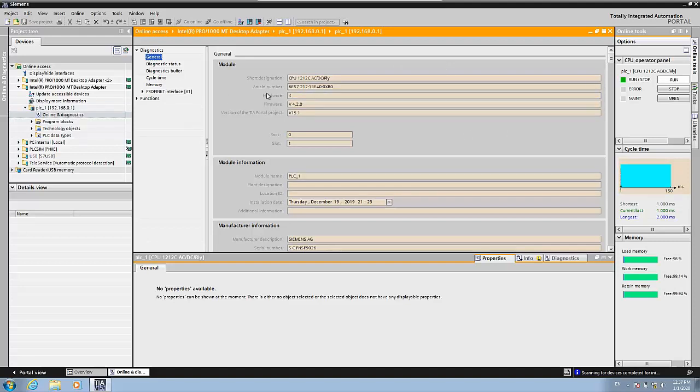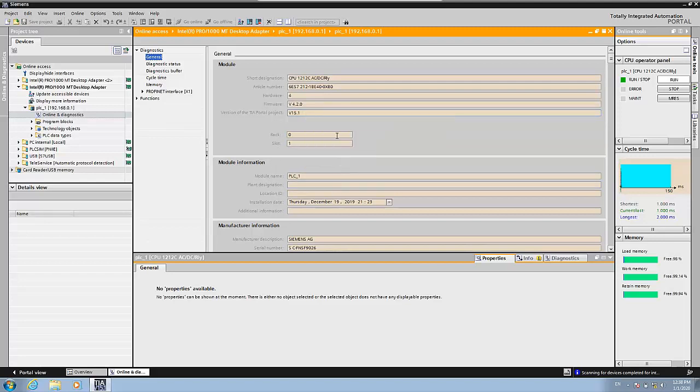So you can check in the first ones that says the firmware version is 4.20. And the version of the TIA Portal project is 15.1. This means that the project that is inside the PLC is version 15.1. And basically here you can know exactly which PLC it is.